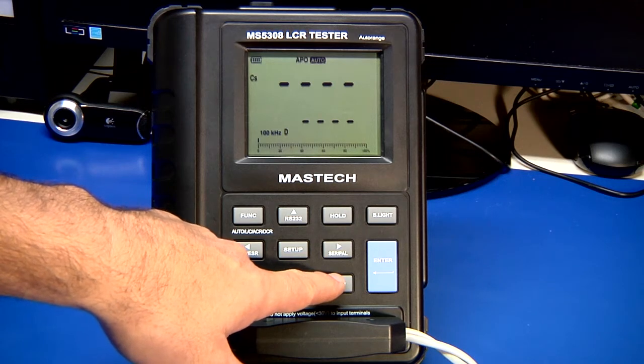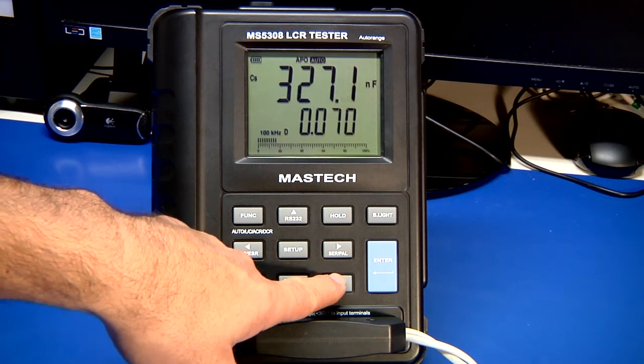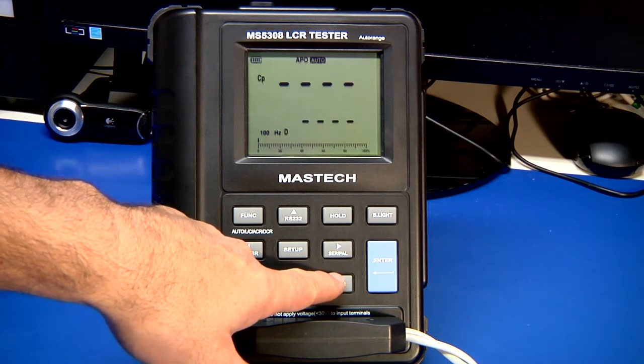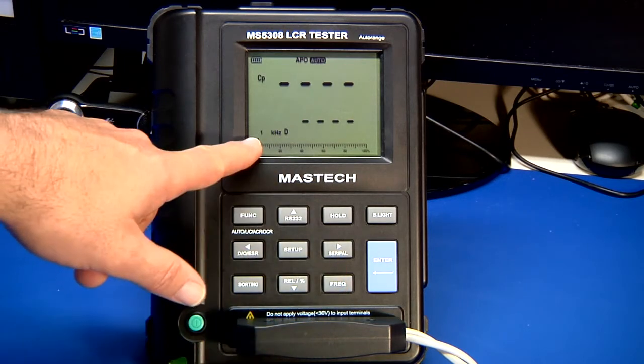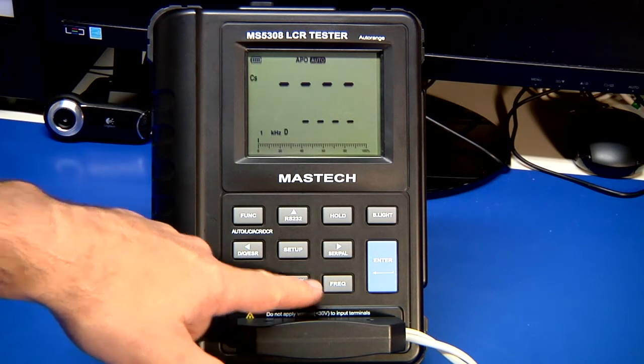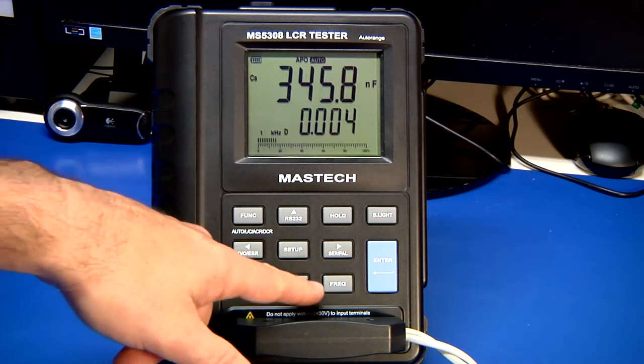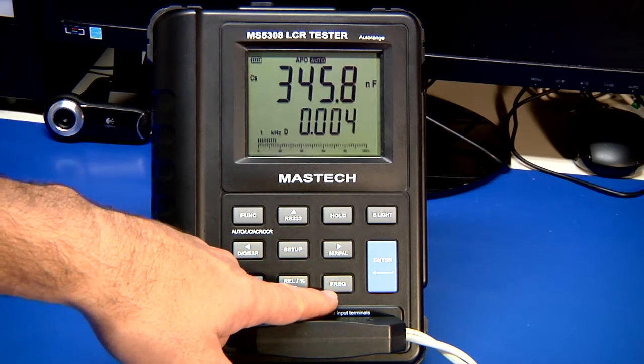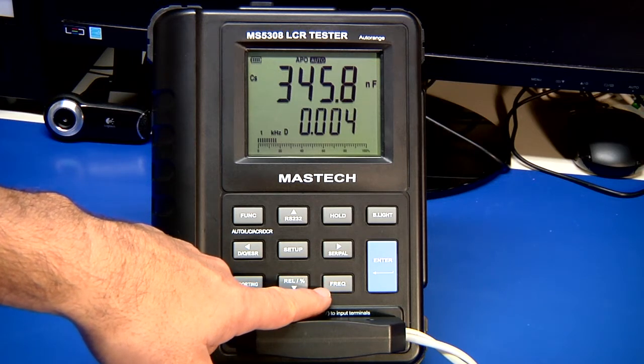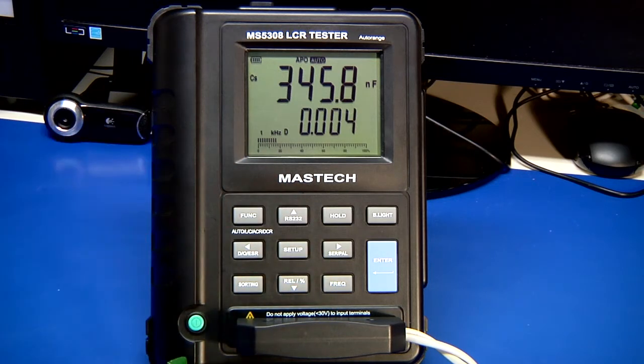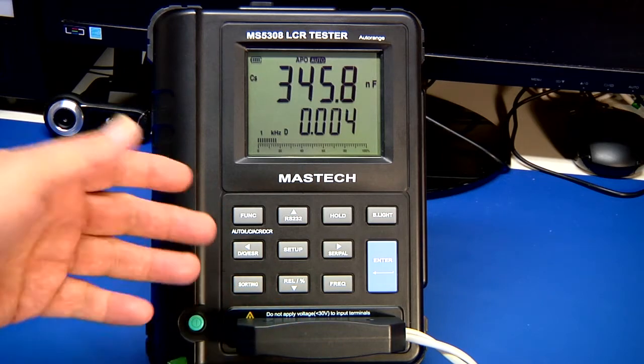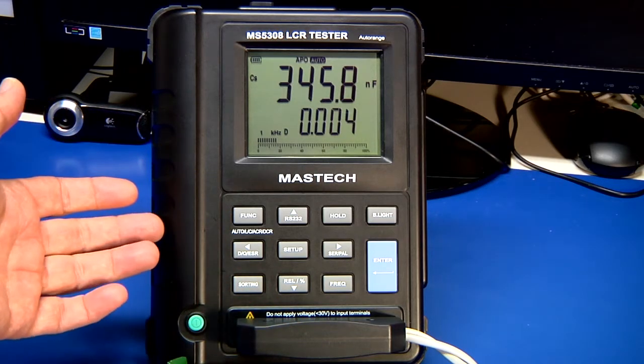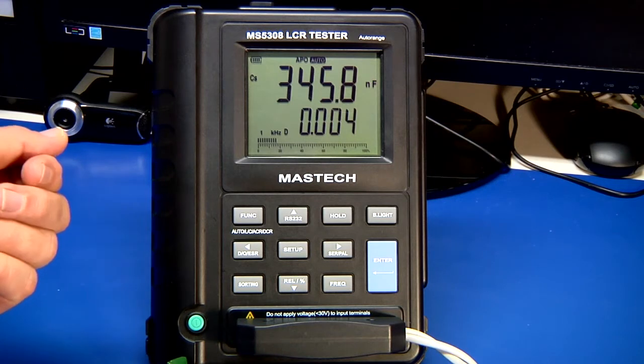Press at 100 kilohertz, and you can just cycle around through each one of these: 100 hertz, 120 hertz, and back to the 1 kilohertz. So the frequency button will cycle through those. Best selection a lot of times, if you have data sheets or something, is to try to choose a frequency that's either the one they tested at or close to that. Again, there are component analyzers that do much better and can do it at maybe the operating frequency.